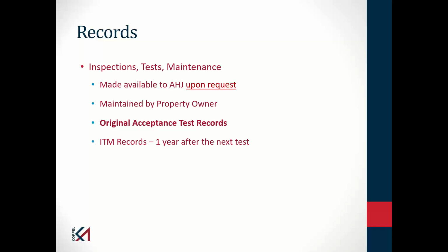Now, again, on the original acceptance test, I can compare that annual fire pump test to the pump performance when it was first installed in your building. And I can make sure that you don't have any overall degradation from that original acceptance of the fire pump. And that addresses the issue of very small decreases in performance every year. Now I can compare it to the original data as well.